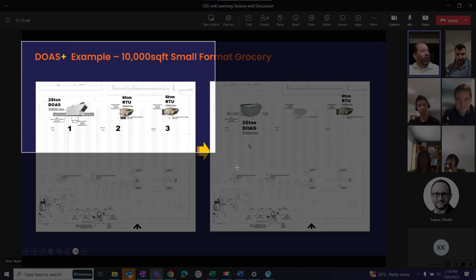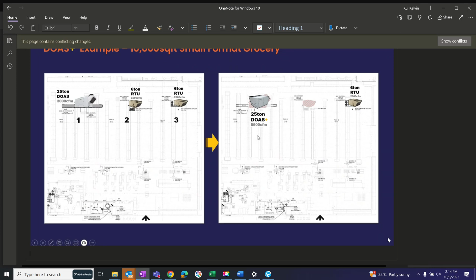So here's the two scenarios. You're right on - we can put in a 25-ton DOAS Plus and eliminate one RTU for free. This demonstrates the point that you take a 25-ton DOAS, make it a 25-ton DOAS Plus, and get 6 tons of free cooling. This is actually in Texas. So in their environment, we get 6 tons of free cooling in our 25-ton box. All the same airflow, same amount of outside air, same amount of recirculating air. We haven't changed anything but consolidated into a DOAS Plus.